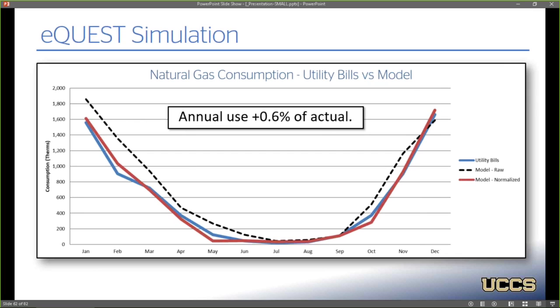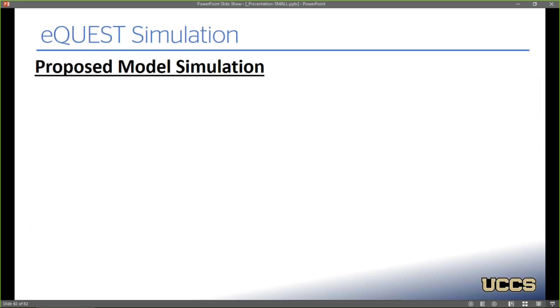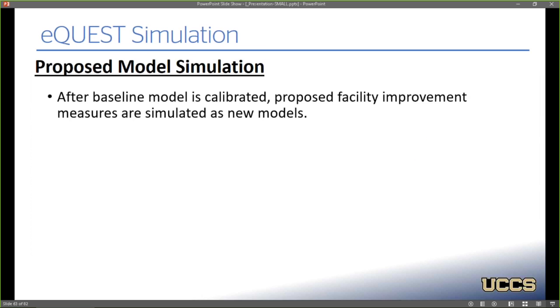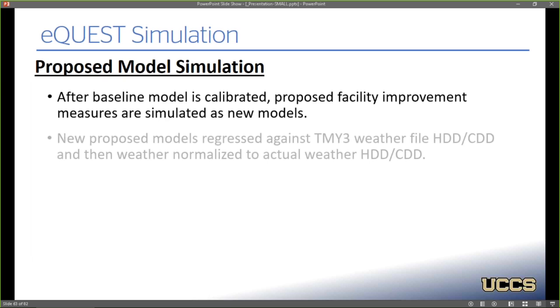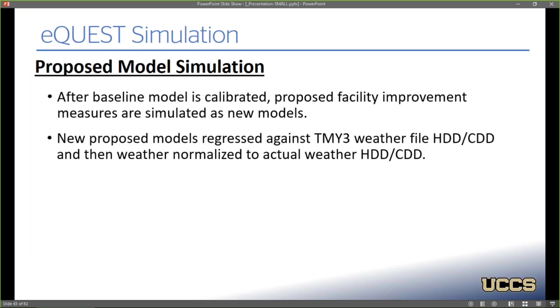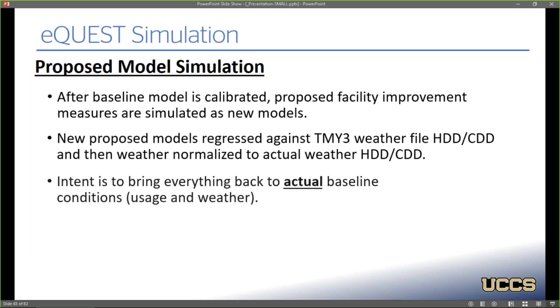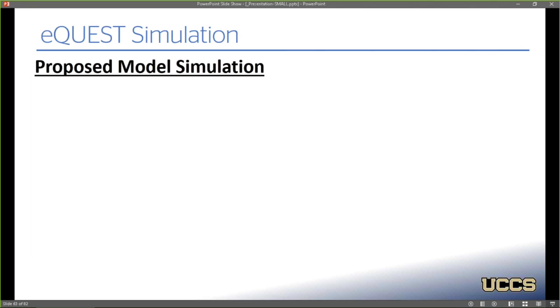And then once the baseline is tuned, we create new models, and then we simulate those as new models. And every model will do its own regression analysis because every model is going to be unique and have a different signature equation. And so each one's going to be normalized. And the intent is to bring everything back to that actual baseline usage and actual baseline weather. And the energy savings are calculated as that baseline use minus the proposed use.